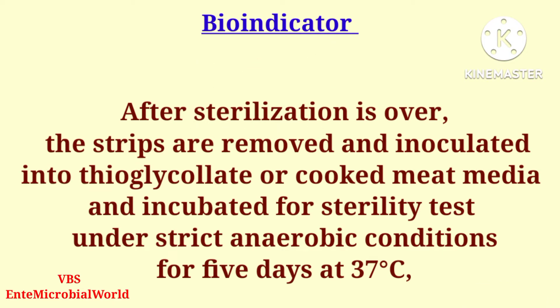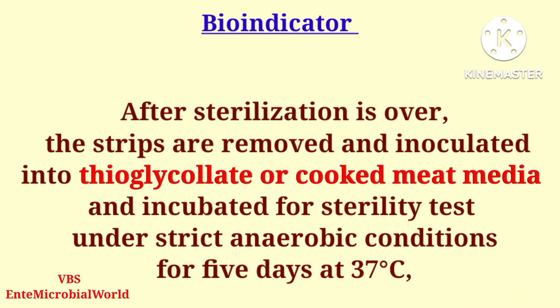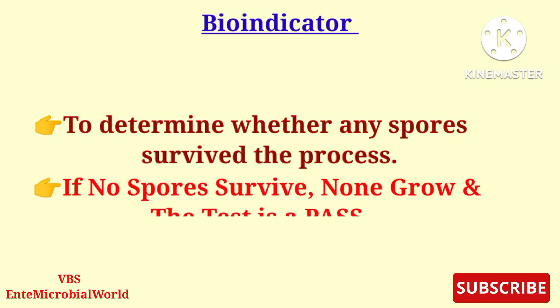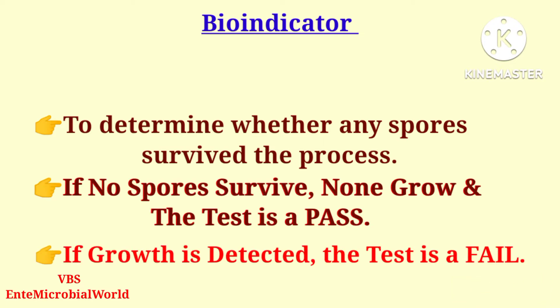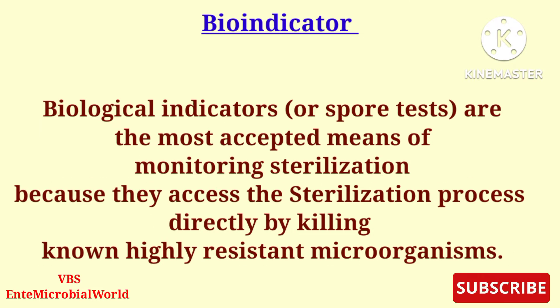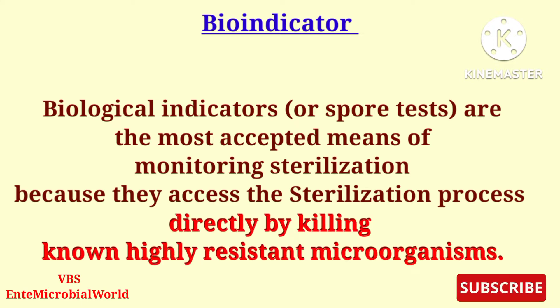After sterilization, the strips are removed and inoculated into thioglycolate or cooked meat media, and incubated for a sterility test under strict anaerobic conditions for five days at 37 degrees Celsius. If no spores survive, none grow and the test is a pass. If growth is detected, the test is a fail. Biological indicators are the most accepted means of monitoring sterilization because they directly assess the process by killing known highly resistant microorganisms.